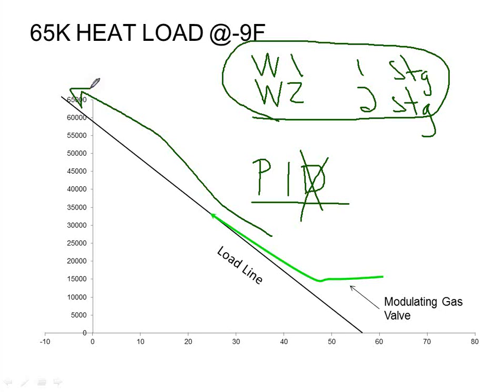I've got 2 different metals connected at some point in that unit, right? 2 different kinds of metal, and they expand and contract at different rates, and eventually they're going to rip apart, and I'm going to get a busted area, and I'm going to get a heat exchanger crack somewhere in that thing. If I keep my gas flowing at a constant rate and I don't turn it on and off, I keep my heat exchanger hot as long as possible, I'm not going to expand and contract as much. And then, at least theoretically in my mind, I should be able to have this thing last longer. So don't think because you're running this thing nonstop that it's going to die sooner. Chances are it's going to last longer than a regular heat exchanger would because I'm not expanding and contracting as much.